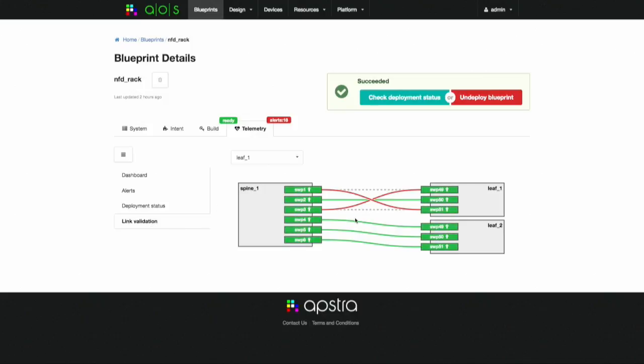And even if you made this page available to a facilities engineer, they would know that they've got these two cables swapped. There isn't the need for, hey, Mr. NOC engineer, get on the console and do a bunch of show commands, and is it cabled to the right place? And you're looking at a spreadsheet to see if it's cabled to the right place, and that spreadsheet may be valid, or it may be an old copy that somebody copied, and that disaster never happens at 3 in the morning. Yeah. And it's like, look, it's a cabling problem. Swap it back.